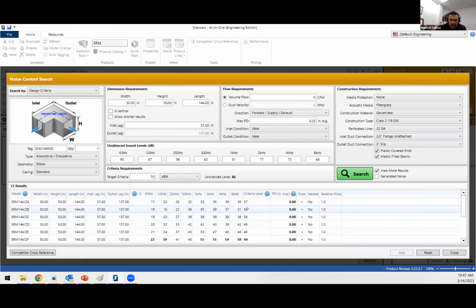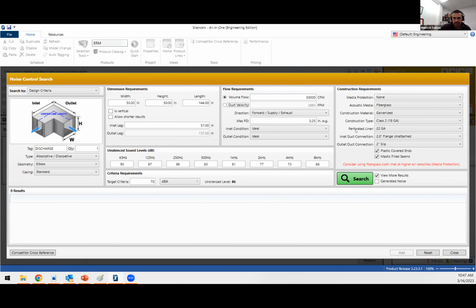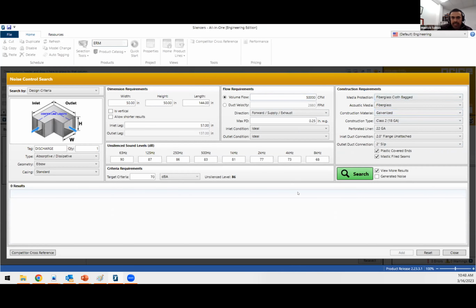And when you look at that already, it's telling you that if you size any of these silencers here, you're meeting the design goals you wanted by bringing it below 70 dBA. Now, one thing I didn't tell the software is that this thing has 50,000 CFM going through. Now, what happens when you do that? The software right away tells you, consider using fiberglass cloth liner at higher velocities to avoid media erosion. So right away, it's letting you know, hey, you need to protect that because it's a lot of air you're trying to put through the silencer.